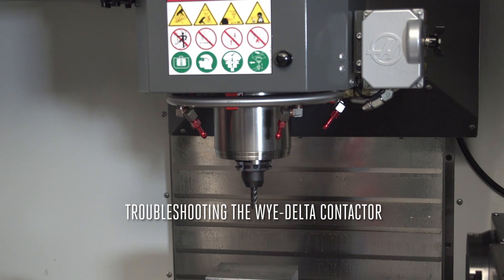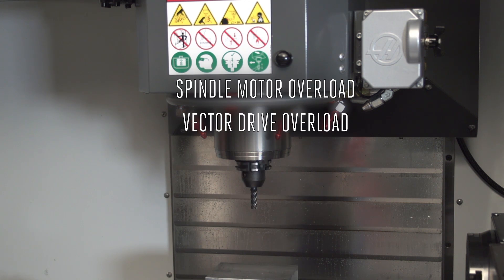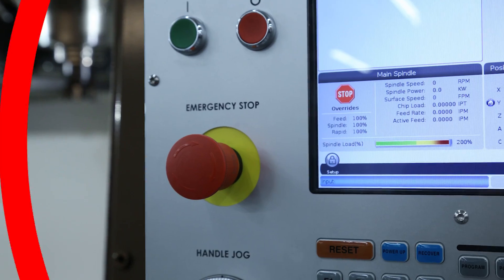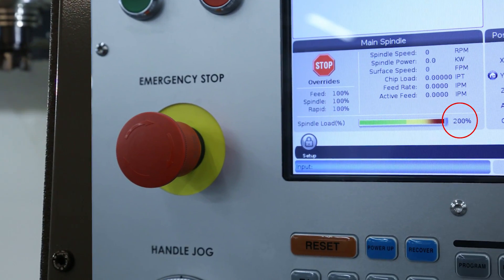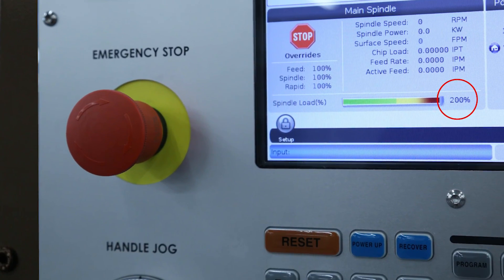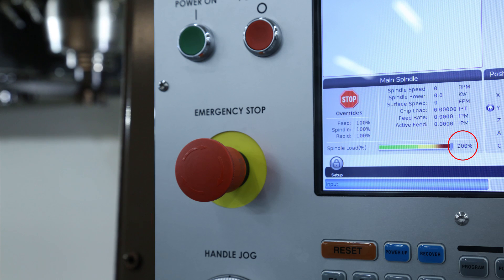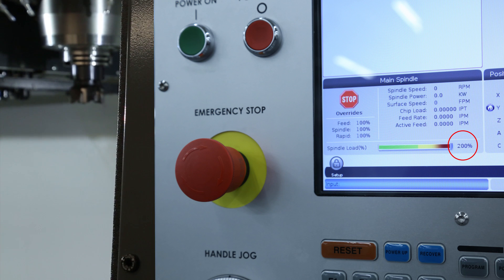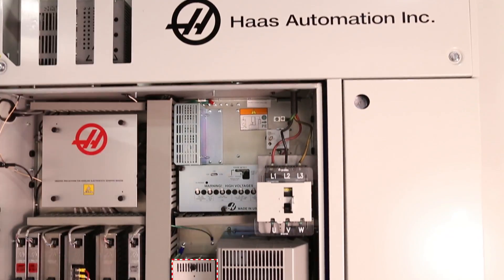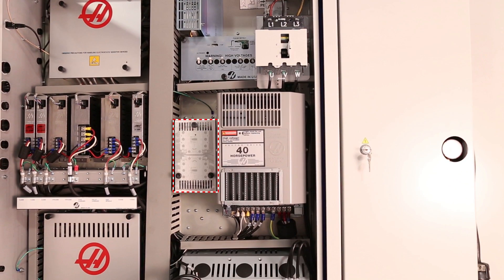If your Haas machine encounters a spindle motor, vector drive, or spindle amplifier overload situation, or if the spindle load remains consistently way above 100%, or if you notice that the spindle load meter pegs out at 200% but the spindle isn't turning, you might have trouble with your Y-delta contactor.